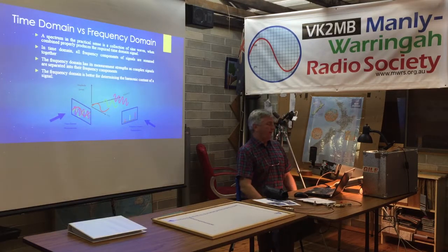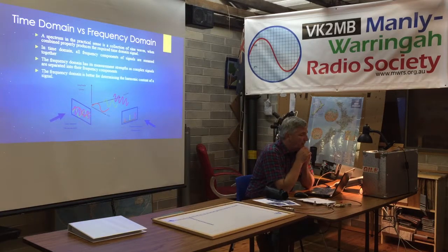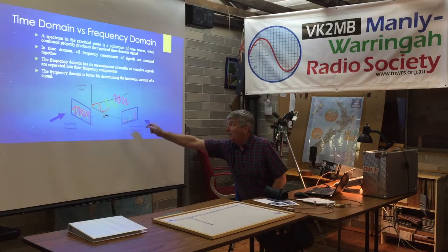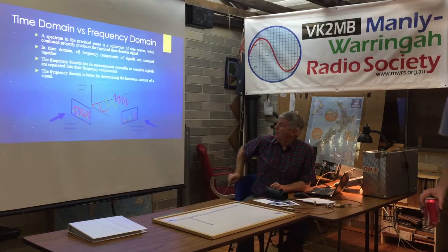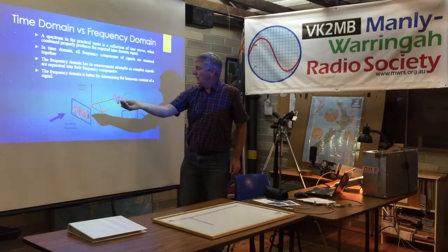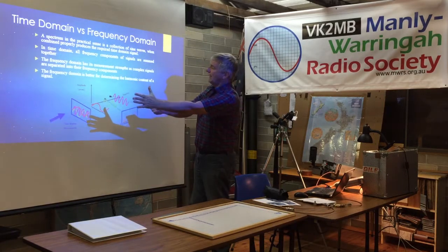So, spectrum analyzers. To try to explain them, you have to get your head around the difference between time domain and frequency domain. What this drawing is trying to display is a three-dimensional drawing with amplitude in this axis, frequency going away from you, and time in this axis. So if you look front on, looking into this...